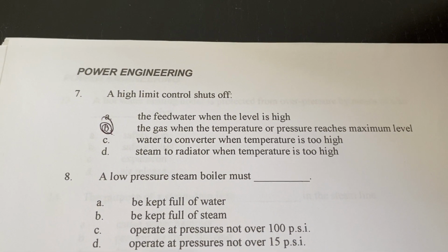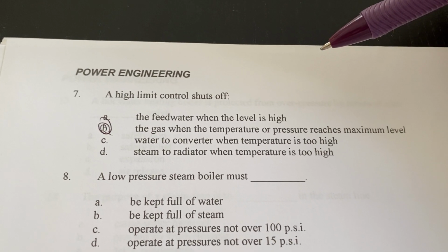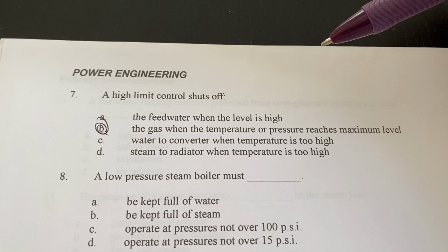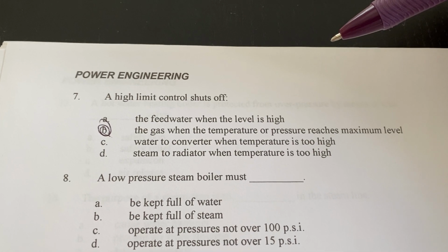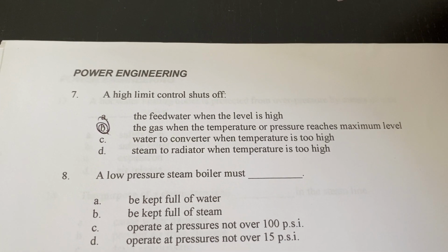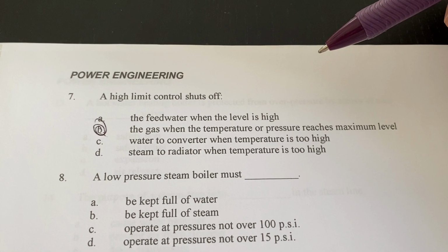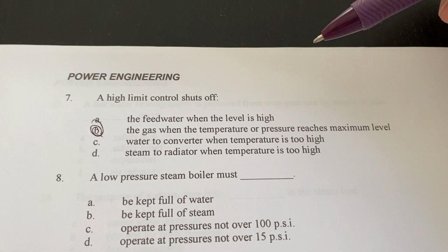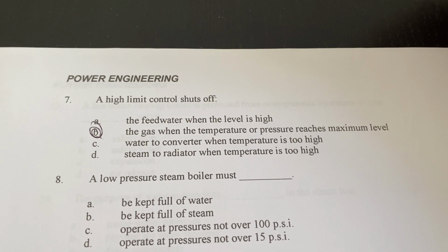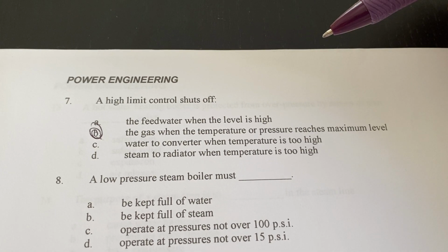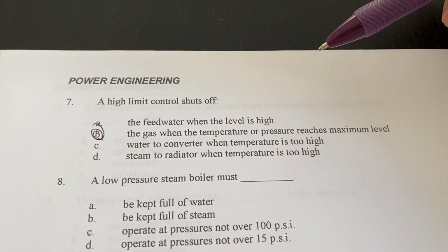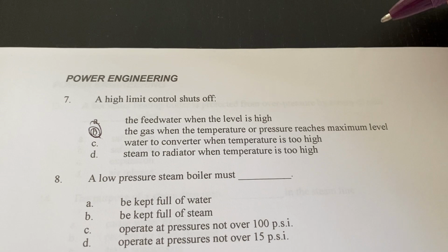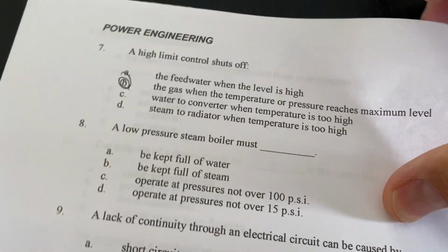High limit switch, okay, so you will set the high limit switch for the maximum that you want it. That's below the safety valve, so you don't lift the safety valve, okay? And that switch will shut off the boiler, so the pressure will not keep increasing. And that switch is mainly a manual reset switch, so the boiler will shut it off and will not turn it on again. You have to go there and press the button to reset the high limit switch.